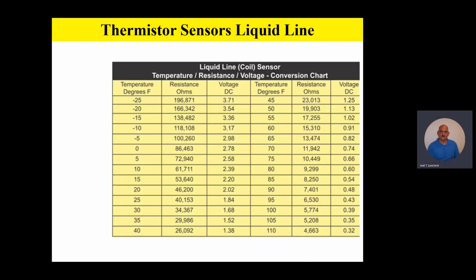Okay, let's take a look at that liquid line or that coil sensor. Now, that coil sensor is going to be clamped on a heat pump. It's going to be clamped on one of the outdoor coil passes outside on the heat pump on the outdoor coil. And let's say, for instance, I measure my outdoor coil temperature is 40 degrees.